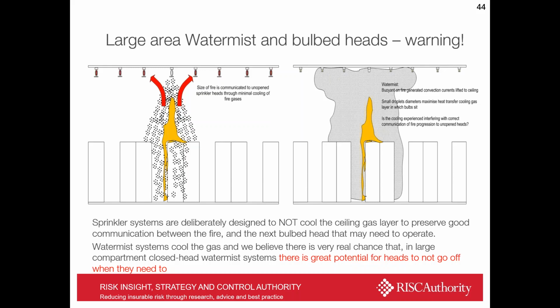However, one of the concerns we have as FPA is that in the water mist arena, commercial protection standards have been written which use the same bulb standards and the like, but we mustn't forget these are very small droplets, and these are essentially gas cooling systems. We don't believe that sufficient work has been done to consider whether one head activating can then impair the ability of the next head to operate, even though it's required, due to cooling of the gas at this height. So we currently feel that the commercial water mist installation standards for systems of this type should be treated with great caution.